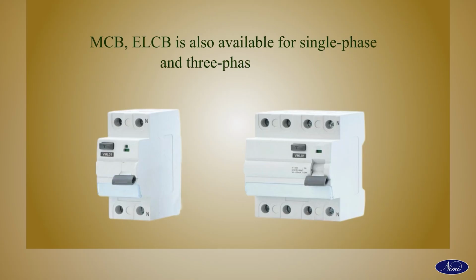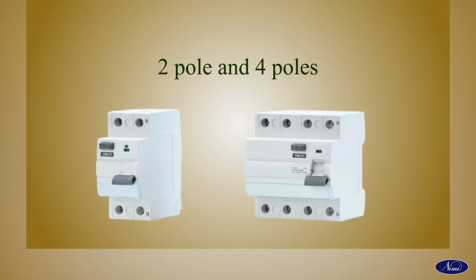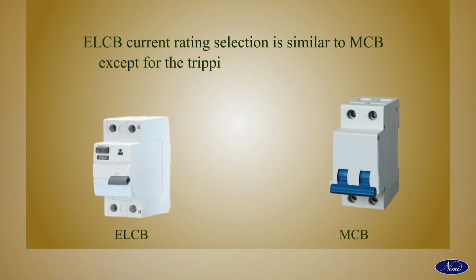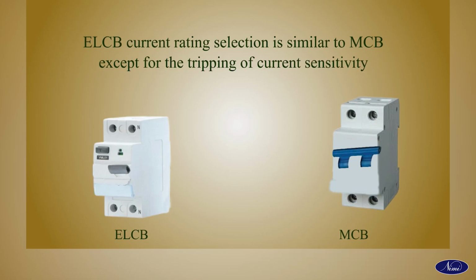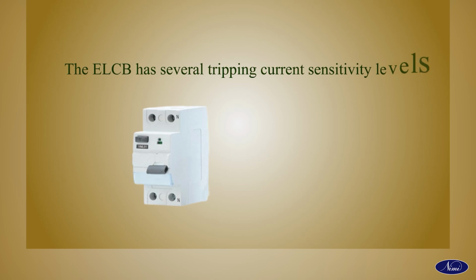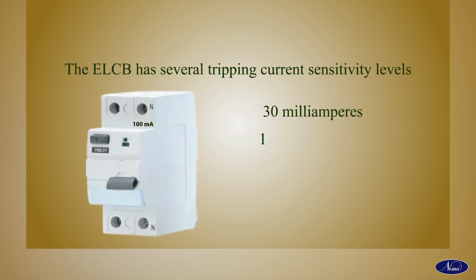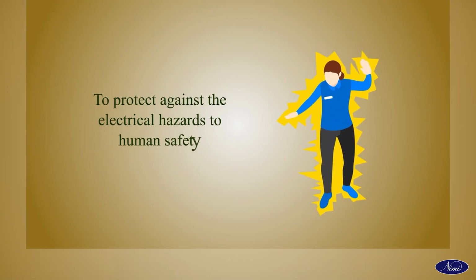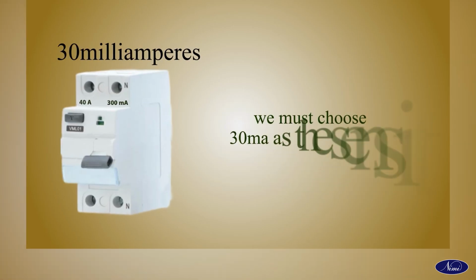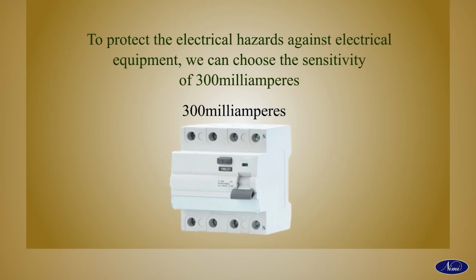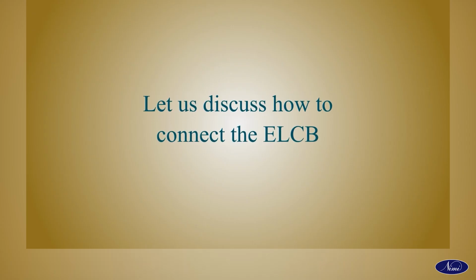Like MCB, ELCB is also available for single-phase and three-phase circuits, like 2-pole and 4-pole respectively. ELCB current rating selection is similar to MCB except for the tripping current sensitivity. The ELCB has several tripping sensitivity levels, including 30 mA, 100 mA, and 300 mA. To protect against electrical hazards to human safety, we must choose 30 milliampere as the sensitivity, and to protect electrical equipment, we can choose the sensitivity of 300 milliampere. Let us discuss how to connect the ELCB.